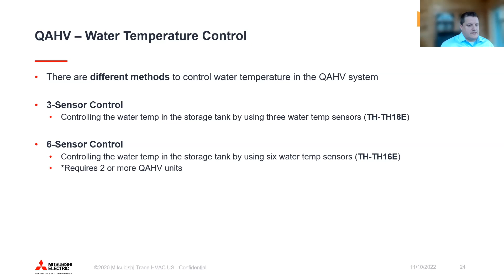So if you look at the 3-sensor control, what this basically means is, and these are just our names for the sensors, TH15, 16, 17. What this basically means is as your storage tanks deplete, and let's say you get down to 130 degrees at TH15 here, that's going to be the signal to turn on the heat pump.